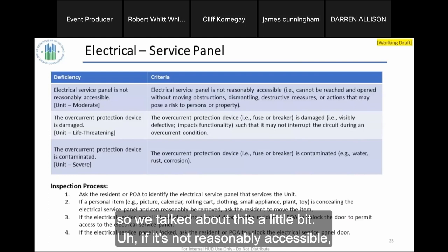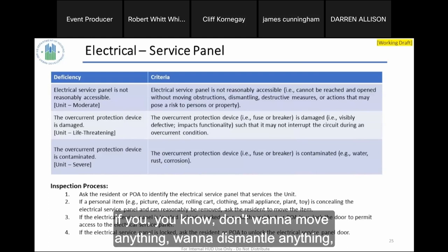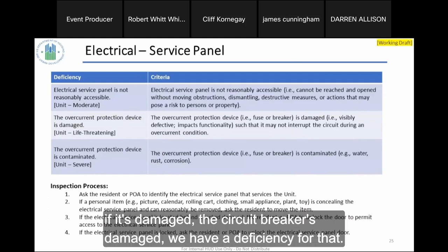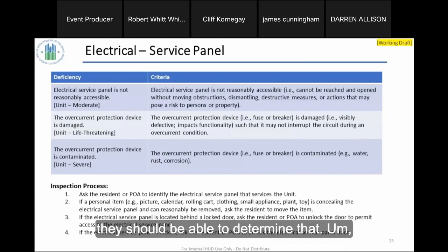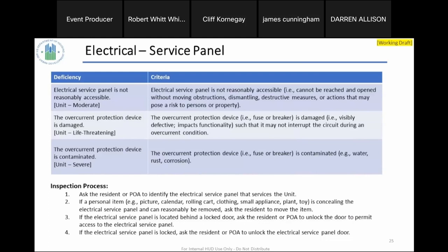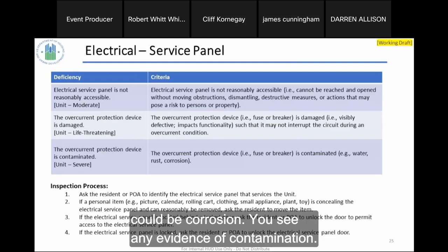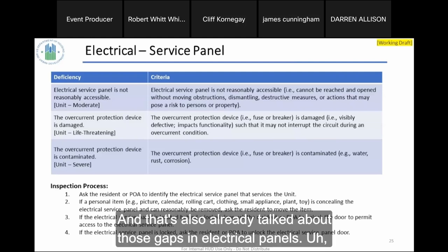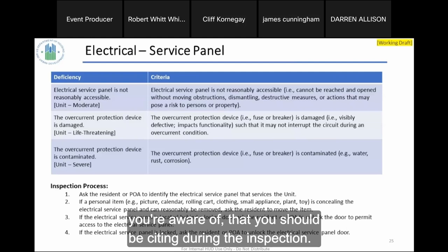If the electrical panel is not reasonably accessible, you should cite that. We've had some pictures about that in the past. Don't want to move anything, dismantle anything, or take any destructive measures. If it's damaged — a circuit breaker is visibly damaged — we have a deficiency for that, which inspectors should be able to determine through professional judgment. For contamination: it could be water, rust, or corrosion. Any evidence of contamination should be cited. This is also where we discussed those gaps in electrical panels — make sure you're aware of what to cite during the inspection.